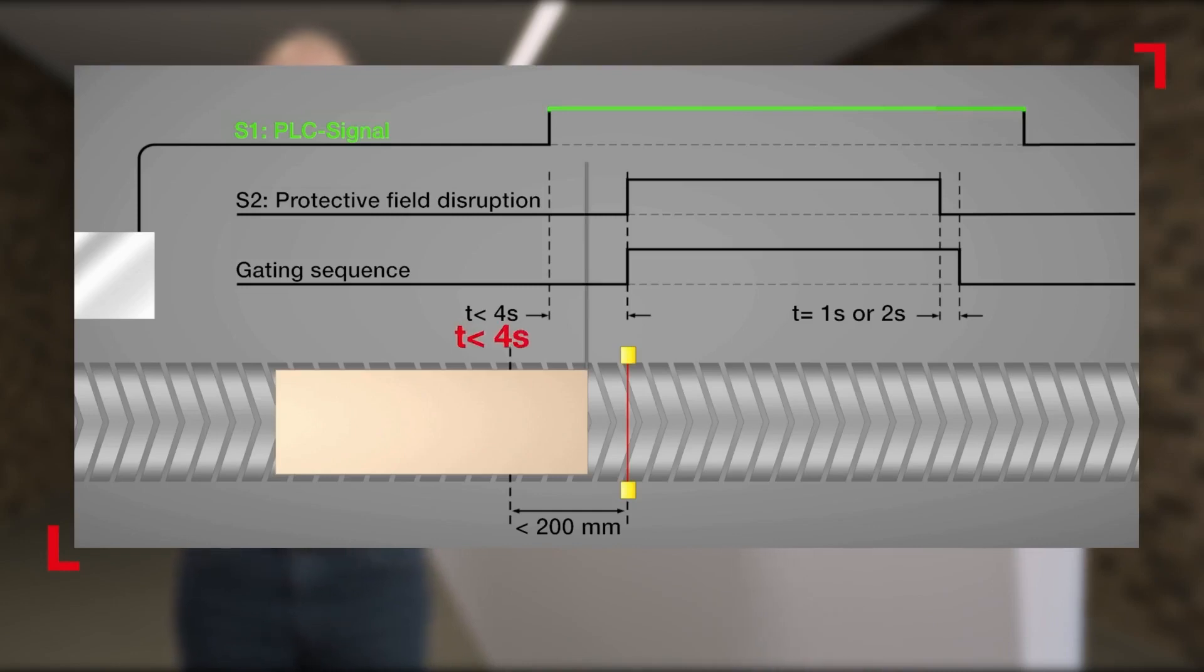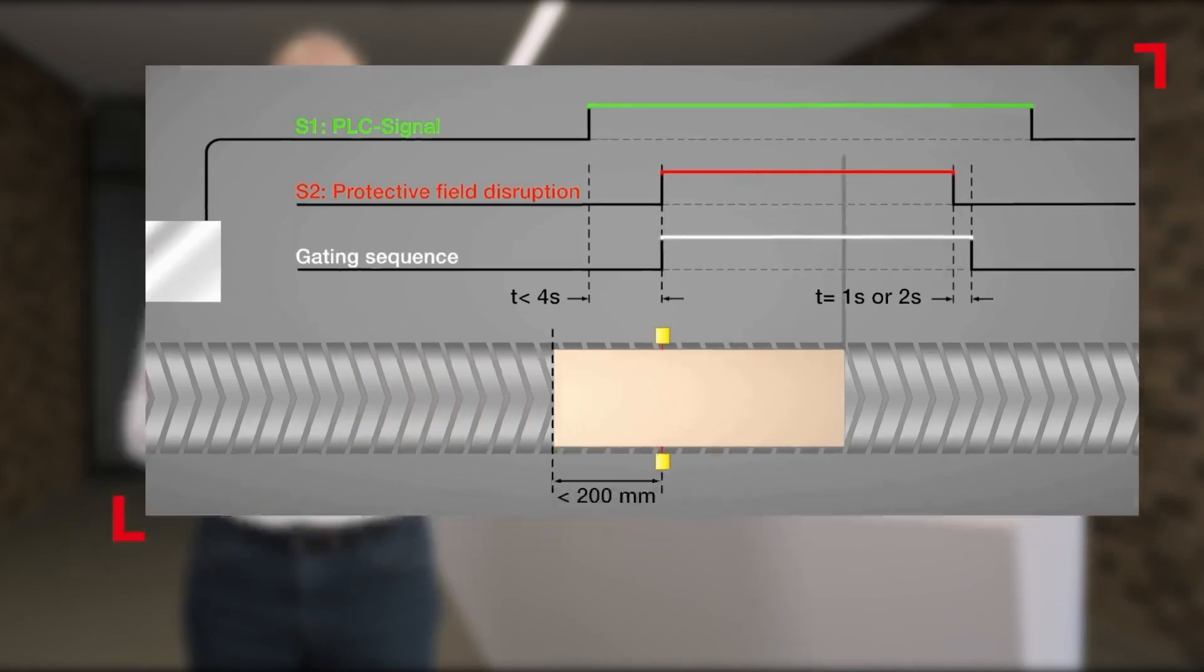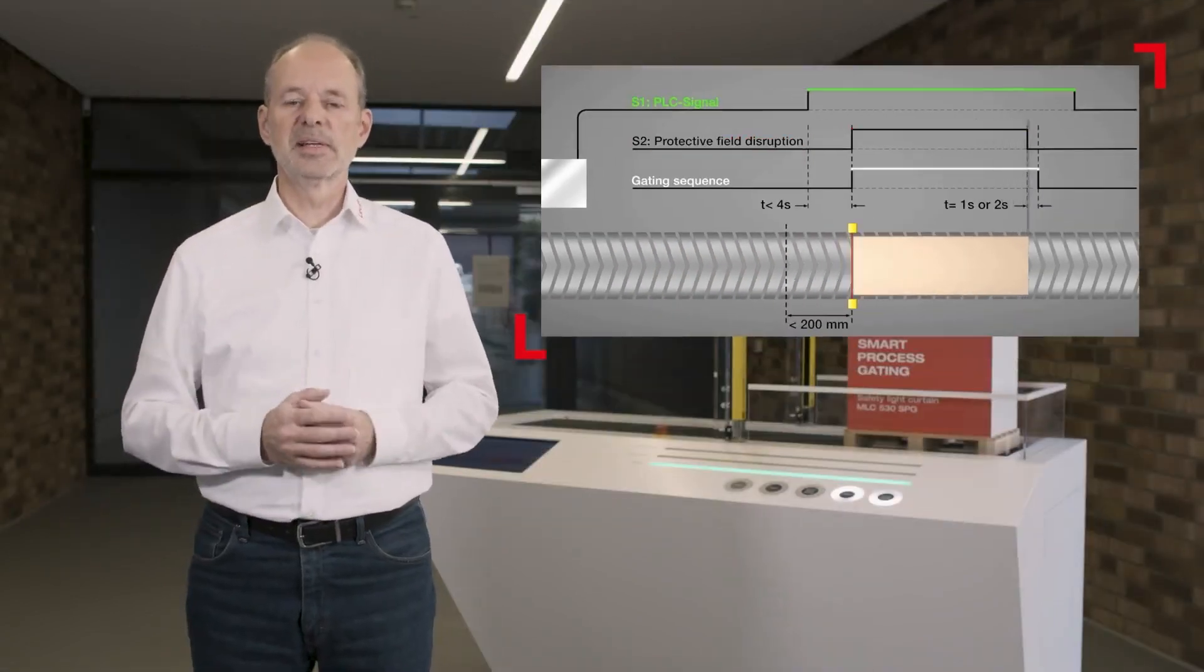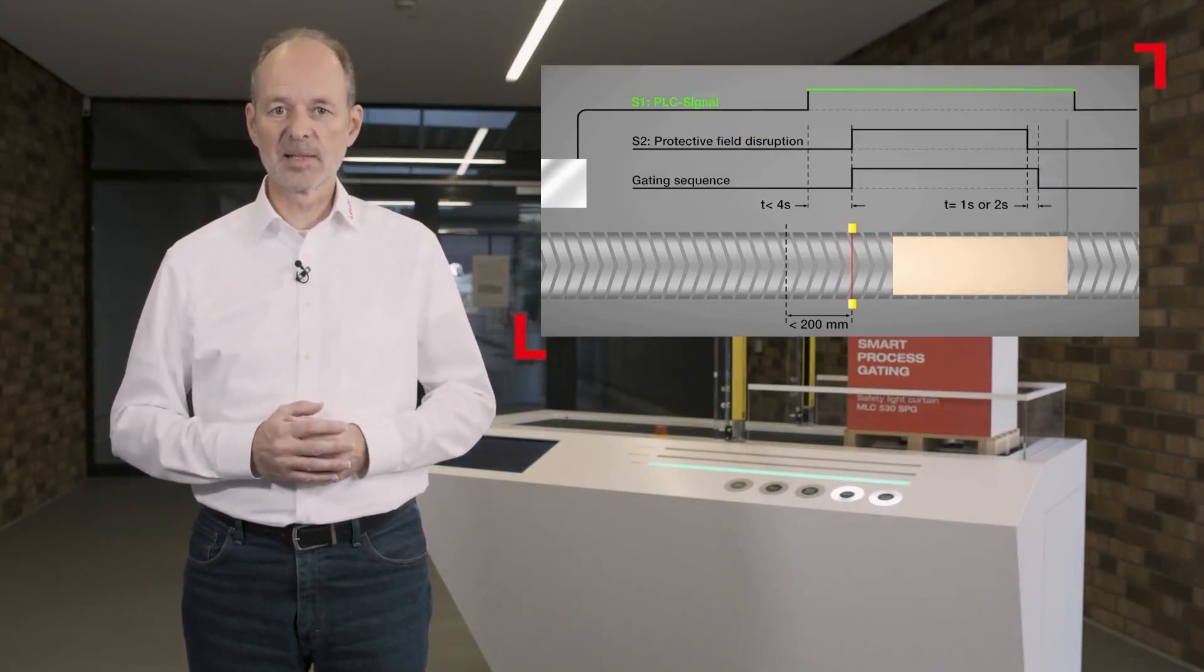In addition, the control signal must not exceed 4 seconds before reaching the safety light curtain to prevent issues. This is due to the safety light curtain being monitored in time. As soon as the transported goods reach the light curtain, the gating function is activated. The end of the gating is automatically set by time or by actively resetting the control signal.